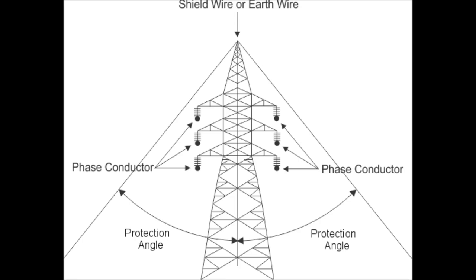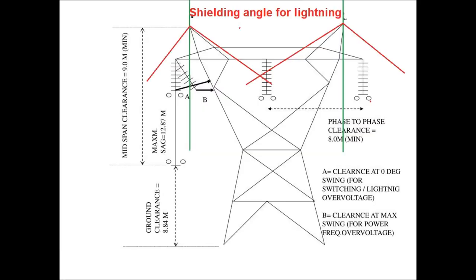If the span between phase-to-phase conductors is more, then instead of one earth wire, two earth wires are used in the transmission tower. Here a 400 kV single circuit tower has been shown in this diagram where two earth wires are used. How the shielding effect is provided by two earth wires has been shown in this diagram.